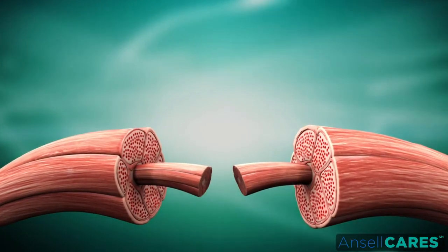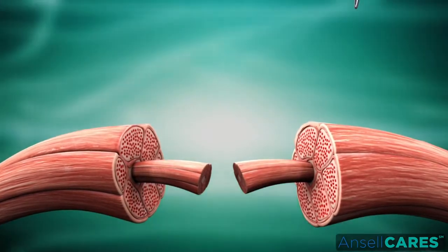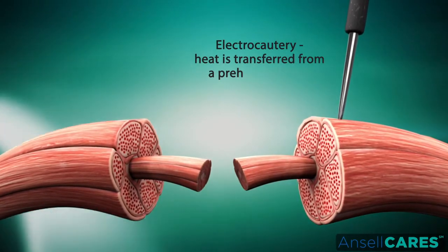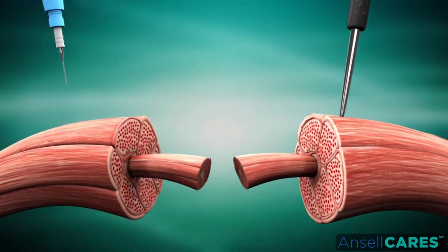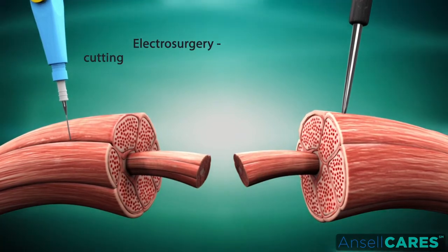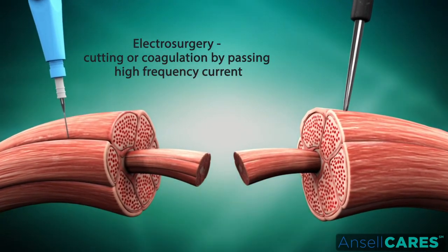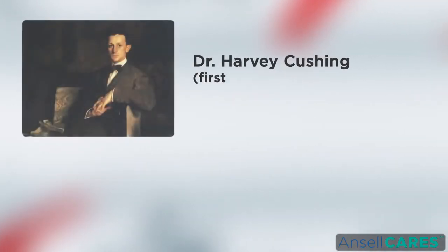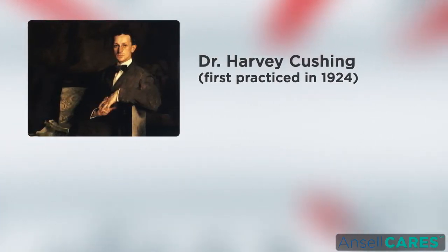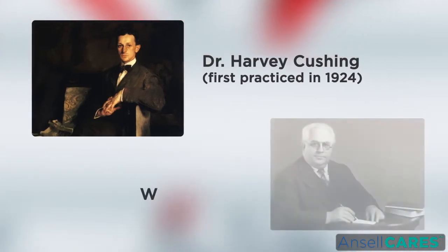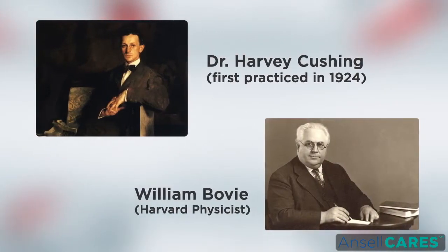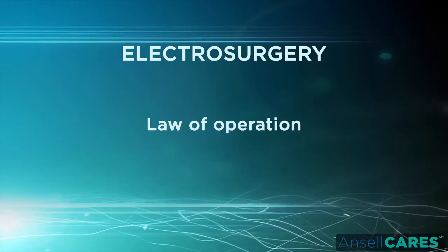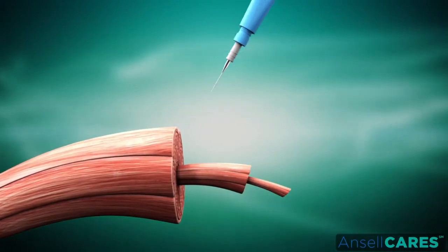Heat was transferred to tissues by contact with the red hot wire. All of these early applications were examples of electrocautery, however not true electrosurgery. In electrocautery, heat is transferred to tissue from a preheated object; the current heats only the electrode and does not pass through the patient's body. True electrosurgery involves the cutting or coagulation of tissues by passing a high frequency current through the target tissue. It was first practiced in 1924 by Dr. Harvey Cushing, a famous neurosurgeon, who enlisted the help of William Bovie, a Harvard physicist — and ever since, Bovie's name has become synonymous with electrosurgical units.